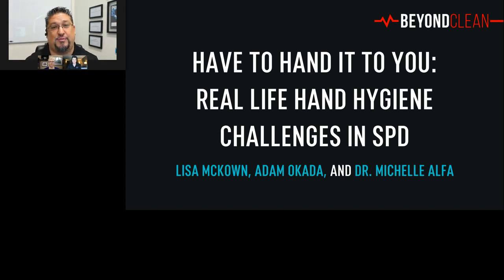When you're going through an automated washer, that's thermal disinfection—that's killing whatever microorganisms are left. Now when you skip that step and go to a hand wash, let's say you do an enzymatic soak, a wipe down, and then pass it through the pass-through window because that's what the IFUs say to do, there's no disinfection step. There's nothing killing the microbes that are still left on that device.